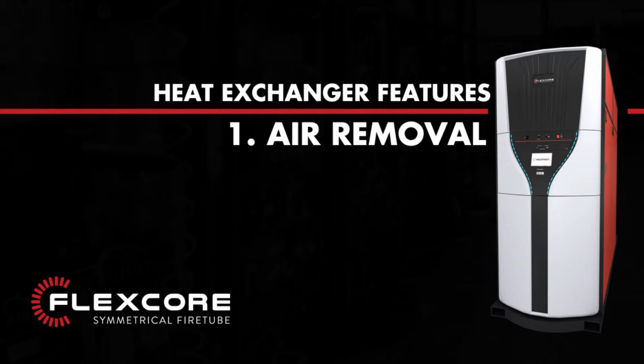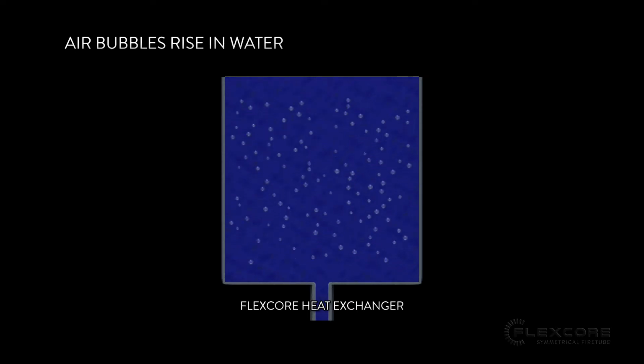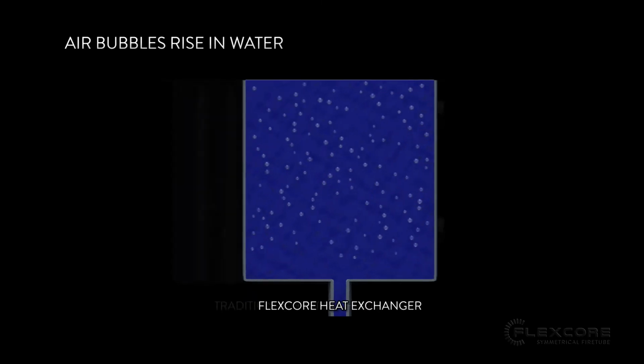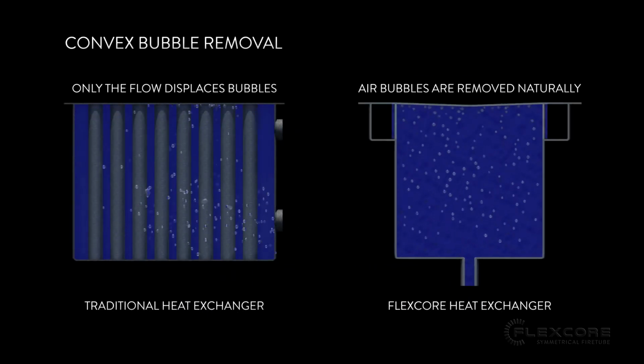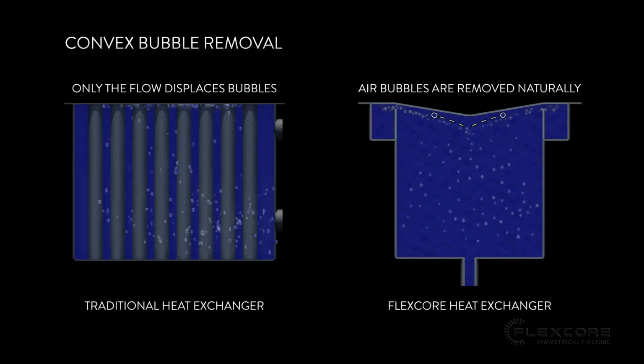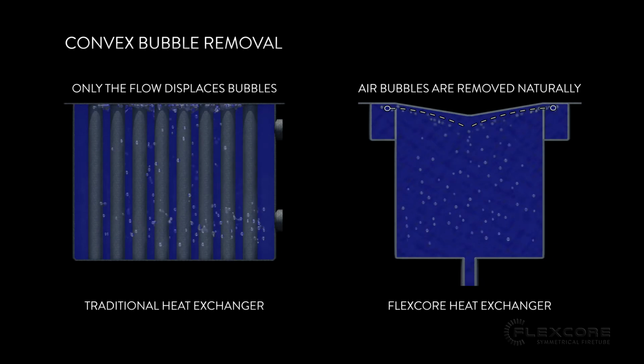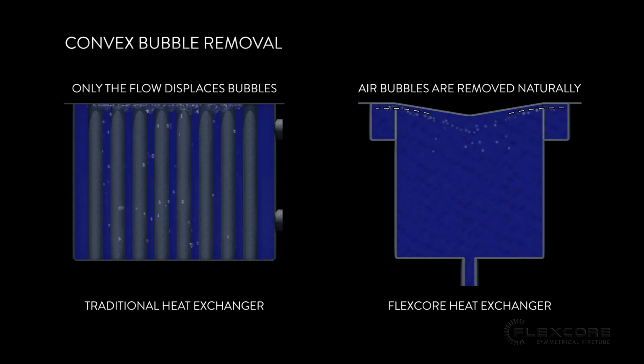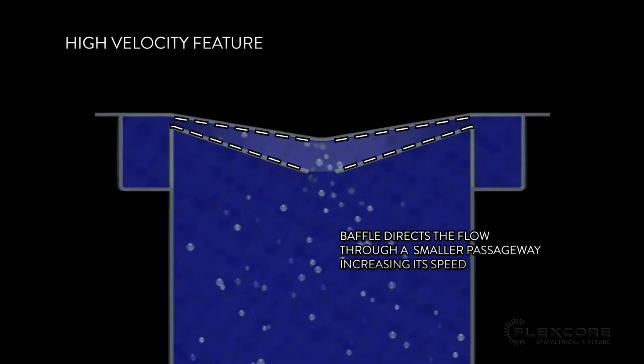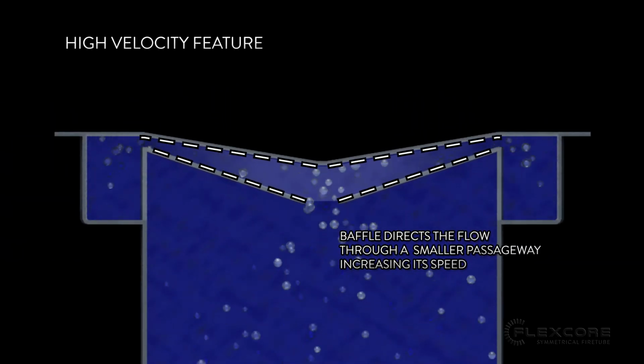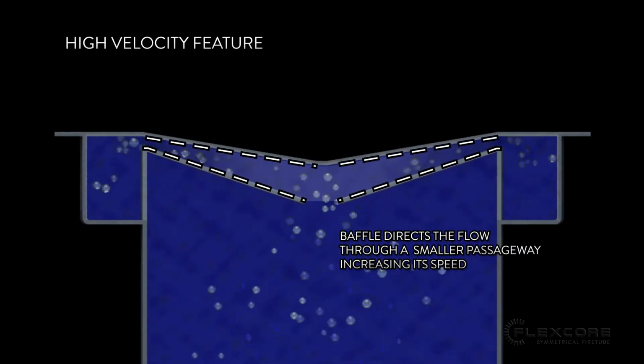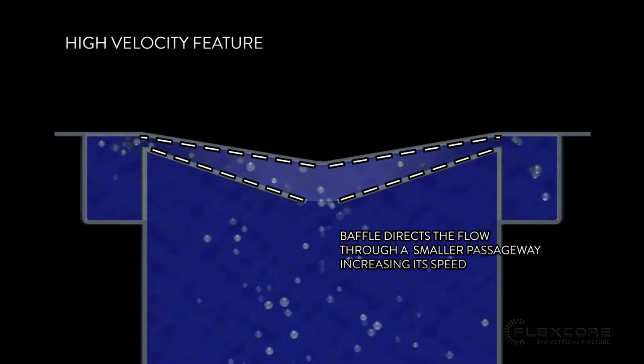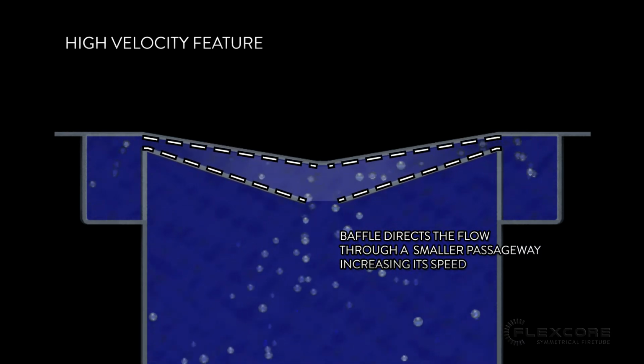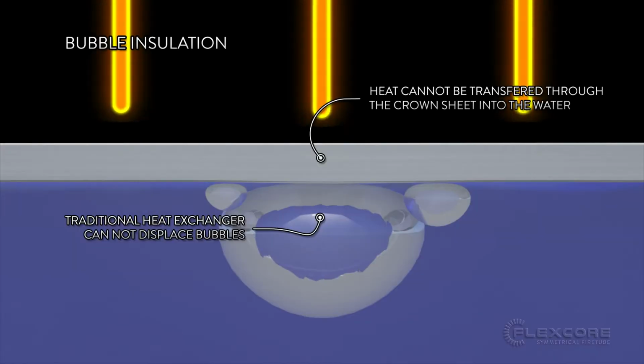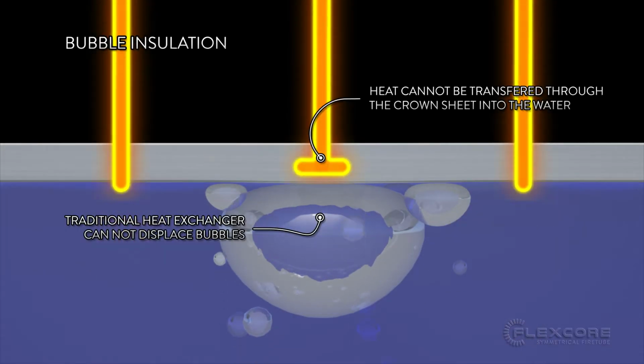1. Air removal. Due to their lower density, all air bubbles are going to rise in water. So the Flexcore's crown sheet has been designed with a convex shape that forces any air bubbles in the water inside the heat exchanger up and away from the middle of the crown sheet. The Flexcore's unique baffle design increases the water velocity across the crown sheet, ensuring that all bubbles are swept away in the flow, even if your system is set to a low pump speed. These features prevent air bubbles from sitting on the crown sheet.